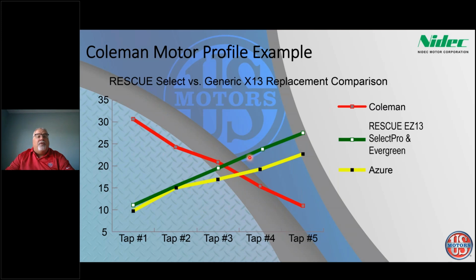That being said, if you have a generic profile motor, which we have, and we know this by checking our airflows—once I install it, I check and say, oh wait, that's cool speed and that's heat speed, and they're completely different than what they should be, knowing what should be high and what should be low.